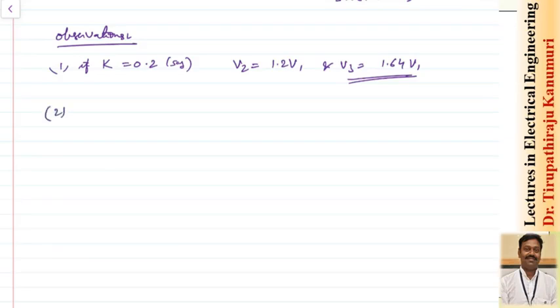So the second observation is, the value of K is equal to C1 divided by C. So as the value of K is increased, automatically the string efficiency will go on falling down. So more non-uniform distribution will be there. This is the second observation.